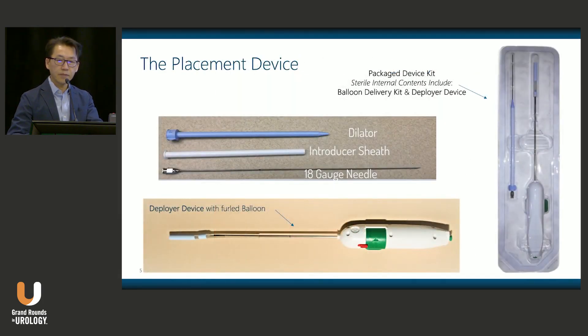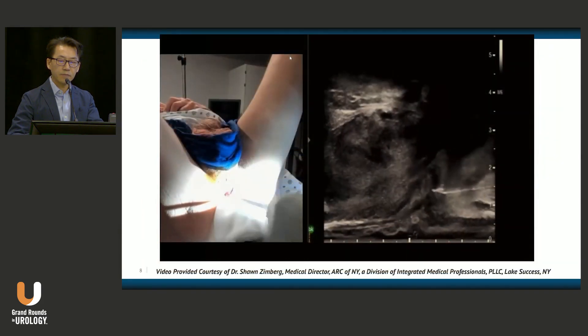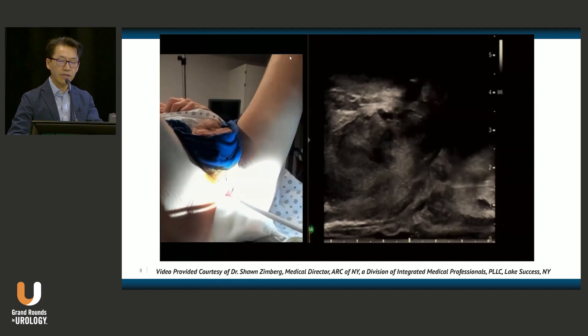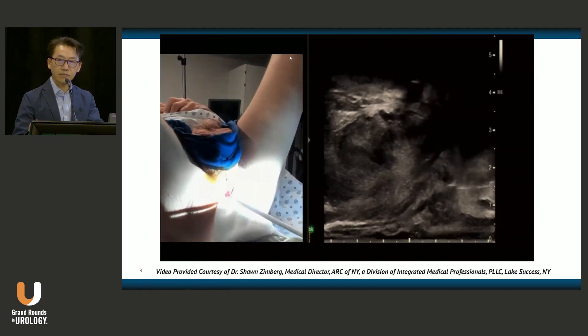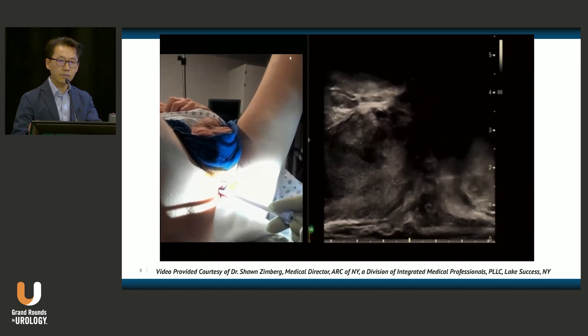Here is a view of the device. It comes with an 18-gauge needle, a dilator, a sheath, and a deployer device with the balloon curled up at the end of it. This is a video from Dr. Shawn Zimberg, who is an early adopter and participated in our multinational trial.